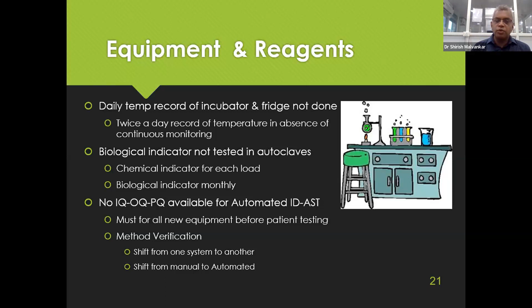Moving on to no IQ, OQ, PQ available for the automated ID/AST system. Now, IQ, OQ, PQ, the installation qualification, the operational qualification, and the performance qualification, should be done for all equipment used for patient testing. Method verification also needs to be done, and it will differ based on whether you are moving from one automated MIC system to another, or from manual disk diffusion to an automated system, wherein you look for the concurrence of data. Close to 90% concurrence is required before you can move from one system to another.